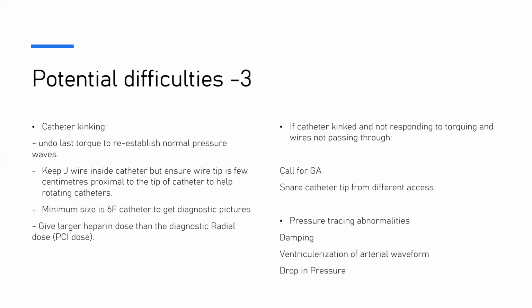It's important not to pass any wire through it. You just have to pull it. You just have to take it out. Don't push anything through the catheter that is damping and moving freely and not showing you any signs of normal pressure back. If your pressure drops suddenly without any reason, then you would question the connections of your system. Your manifold has to be connected properly. Sometimes the connection between the back end of the catheter and the manifold is loose and you don't connect it coaxially. Sometimes the pressure tracing becomes a bit inaccurate. One thing I didn't mention is to make sure that the zero of the patient is done accurately of those arterial lines and to make sure that it's positioned at the level of mid chest of the patient.